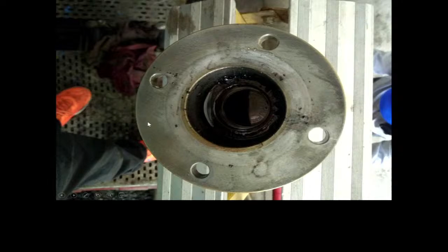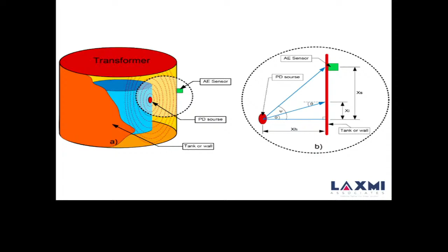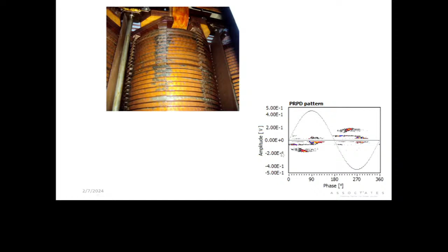Some case study: it's a regulating transformer where PD was conducted, and a severe PD signal was found. Online PD was conducted and the location was also found. After inspection, what we find here is that in the coupling between the rectifier and regulating unit, the coupling is burning. You can see the coupling. That was a quality issue, and the whole coupling was replaced. This was not in one, there are 10 transformers which had such issues, minor or major, and those were replaced.